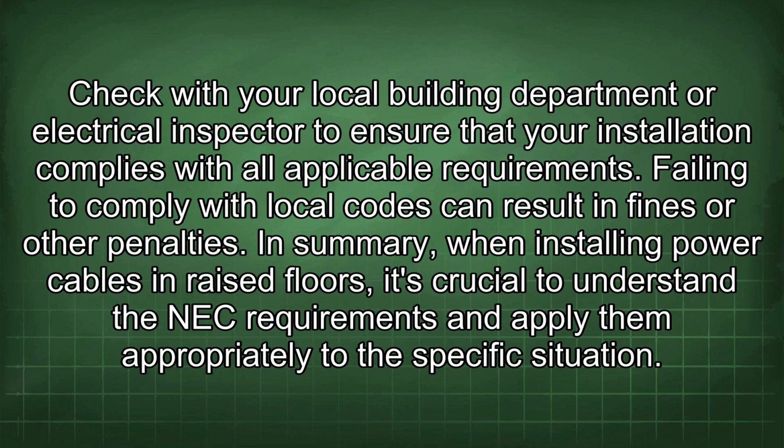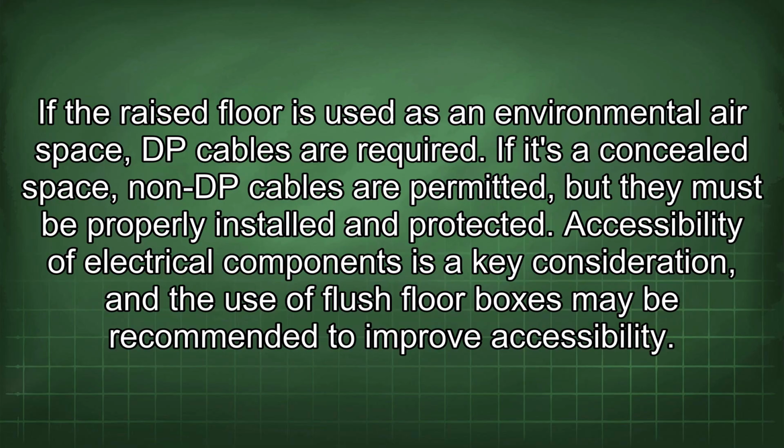In summary, when installing power cables in raised floors, it's crucial to understand the NEC requirements and apply them appropriately to the specific situation. If the raised floor is used as an environmental airspace, DP cables are required. If it's a concealed space, non-DP cables are permitted, but they must be properly installed and protected. Accessibility of electrical components is a key consideration, and the use of flush floor boxes may be recommended to improve accessibility.